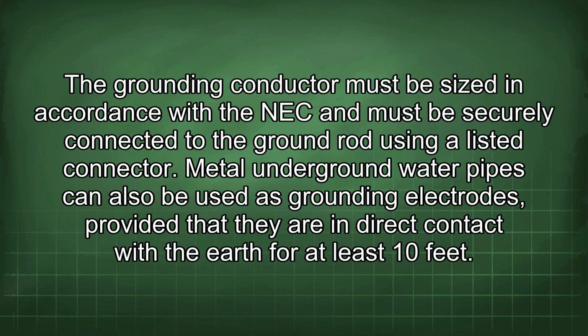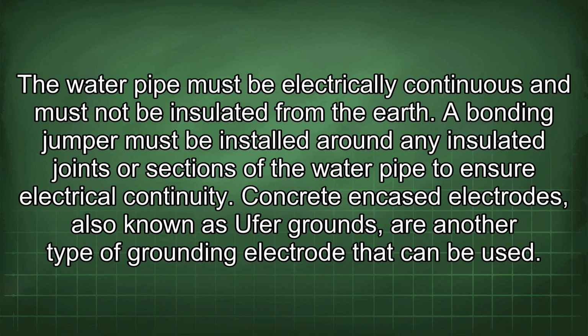The grounding conductor must be sized in accordance with the NEC and must be securely connected to the ground rod using a listed connector. Metal underground water pipes can also be used as grounding electrodes, provided that they are in direct contact with the earth for at least 10 feet. The water pipe must be electrically continuous and must not be insulated from the earth. A bonding jumper must be installed around any insulated joints or sections of the water pipe to ensure electrical continuity.